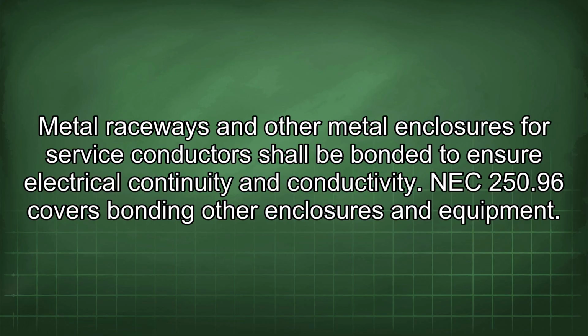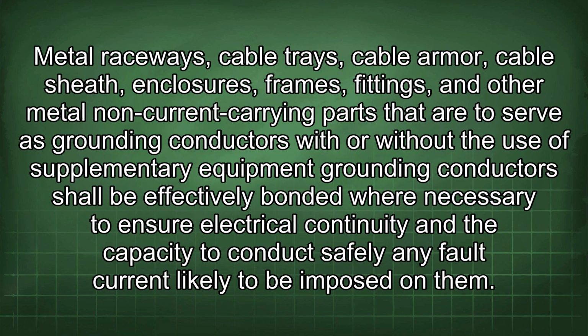NEC 250.96 covers bonding other enclosures and equipment. Metal raceways, cable trays, cable armor, cable sheath, enclosures, frames, fittings, and other metal non-current carrying parts that are to serve as grounding conductors, with or without the use of supplementary equipment, shall be effectively bonded where necessary to ensure electrical continuity and the capacity to conduct safely any fault current likely to be imposed on them.